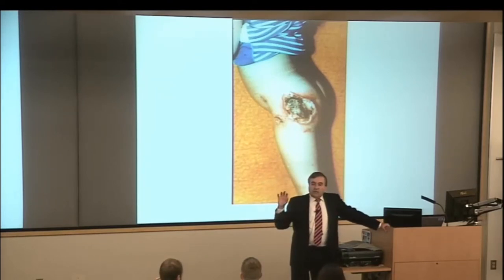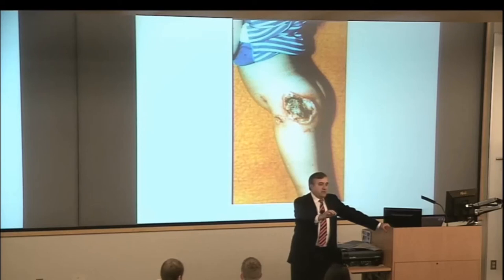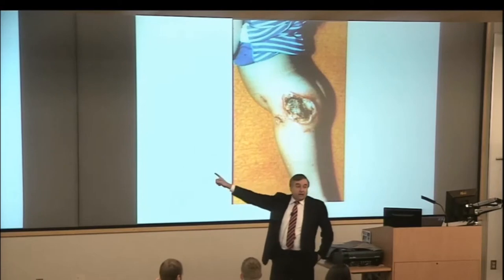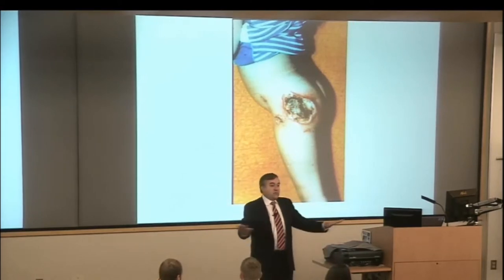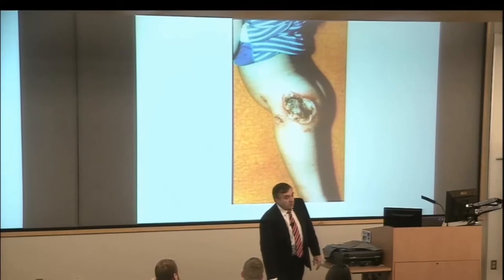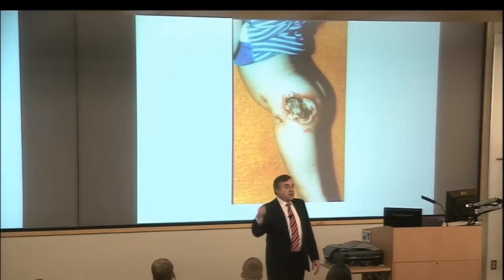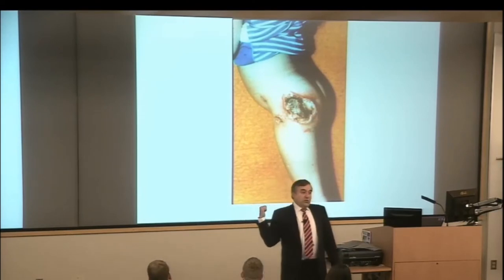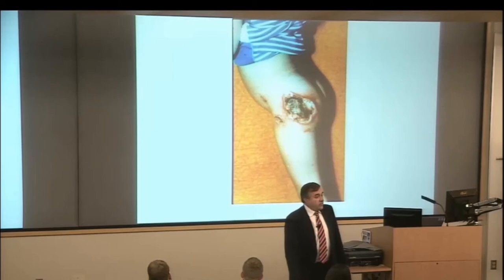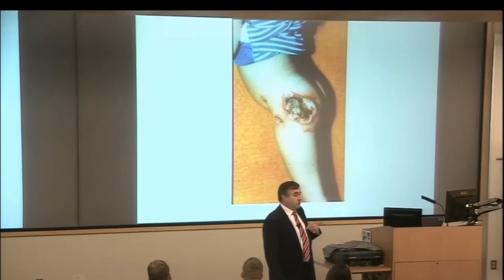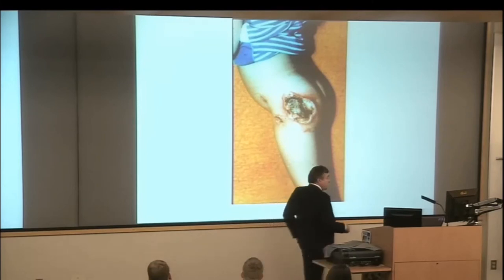The energy you put at your effector device is specifically at the end of a little metal rod, but the same energy goes to the pad. The pad is large because it disperses the energy so there's no heating on the skin. Otherwise, if you put a little piece of metal there and connect it to the returning pad outlet on your ESU, you'd get a burn there—the same burn you get where you apply your Bovie device. So this is a third-degree burn from a return pad that was applied wrong.